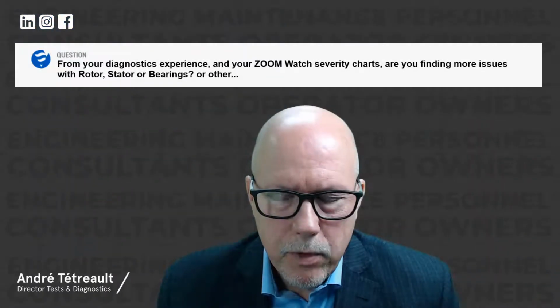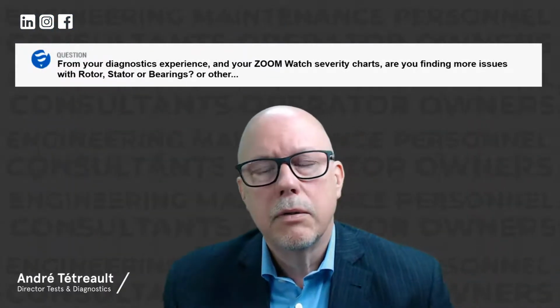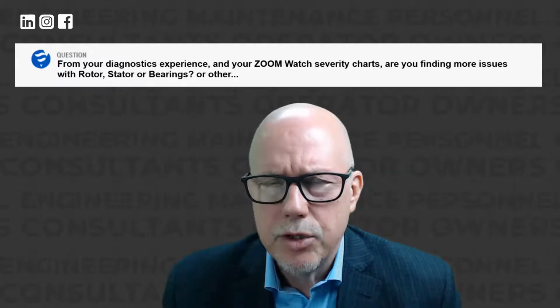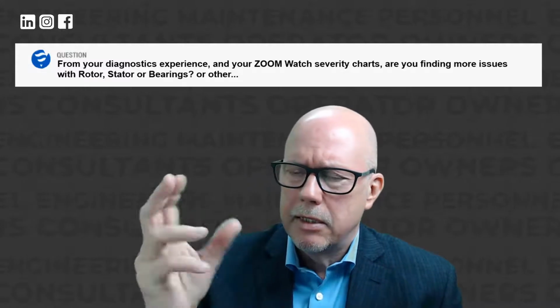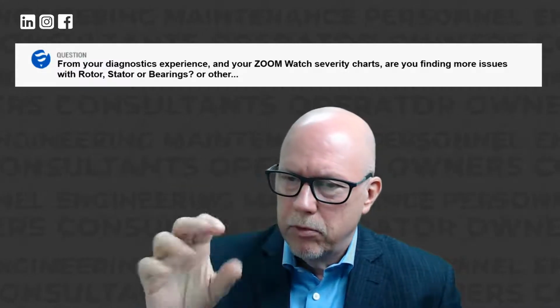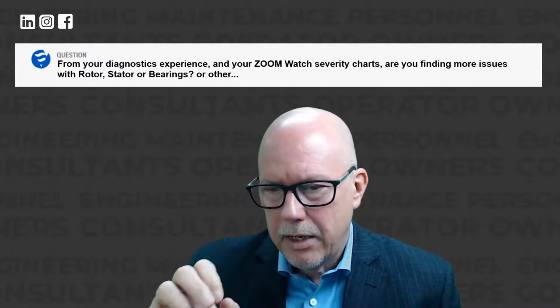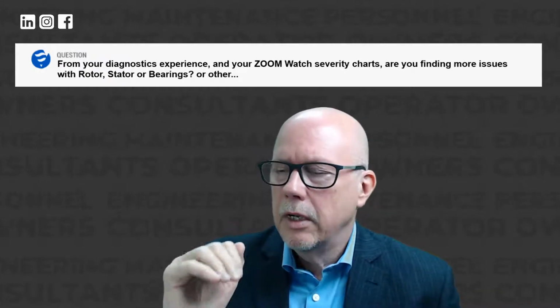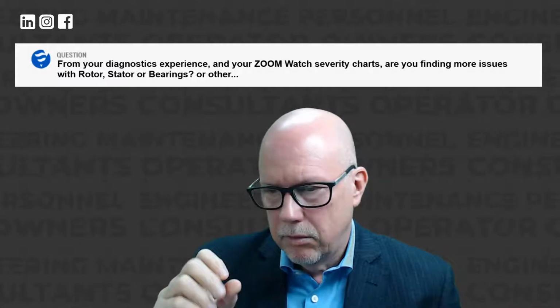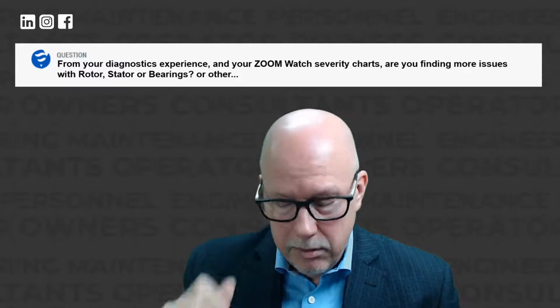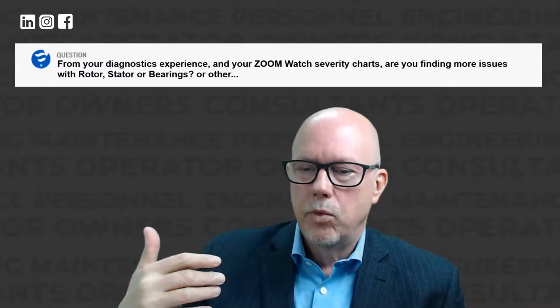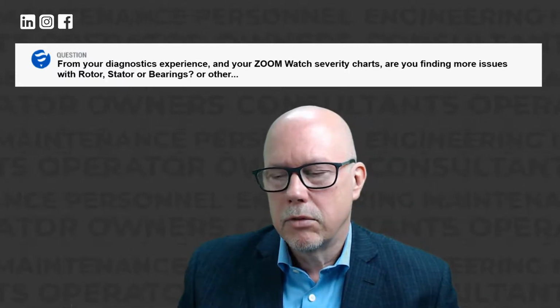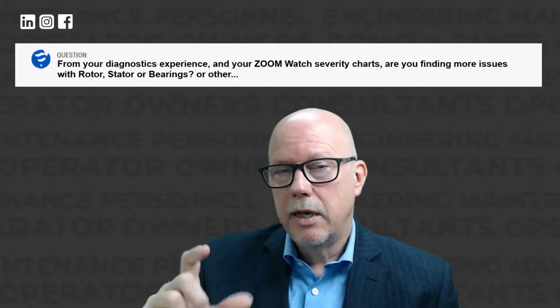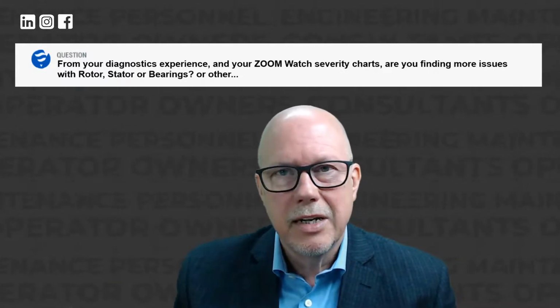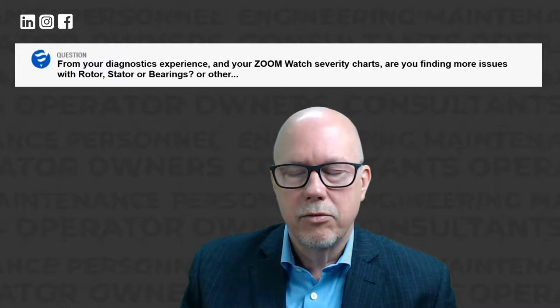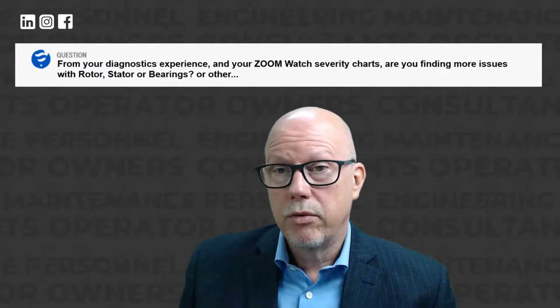Whenever we find issues with bearings, in many cases it's because of the dynamics we see from the rotor and stator. People focus on vibration and immediately think about film distribution, oil distribution, gapping, alignment, and so on, which is all fine. But in many cases, very high vibration levels are caused by the dynamics in the air gap — either the rotor is out of round or not centered, or the stator is out of round. In most cases, it's both.